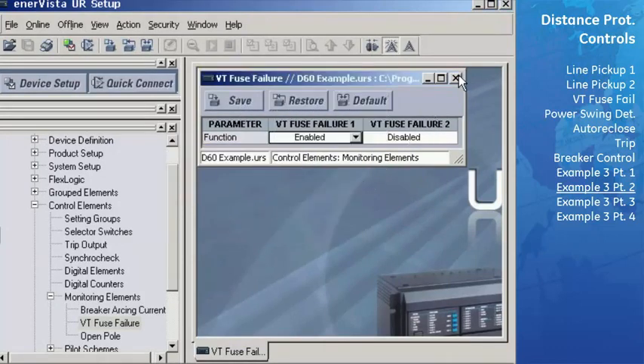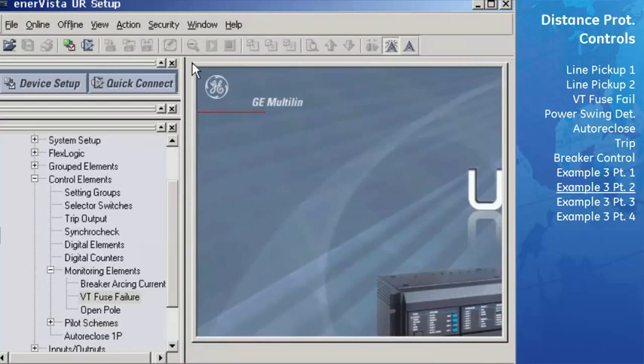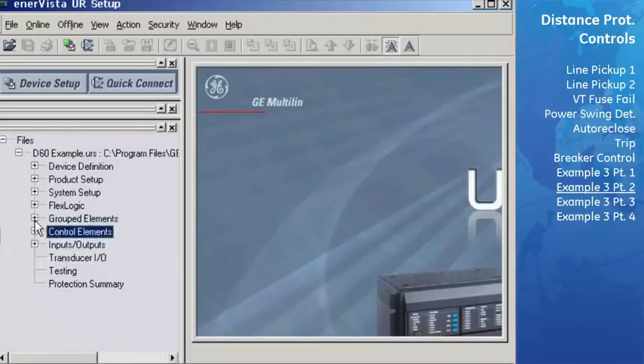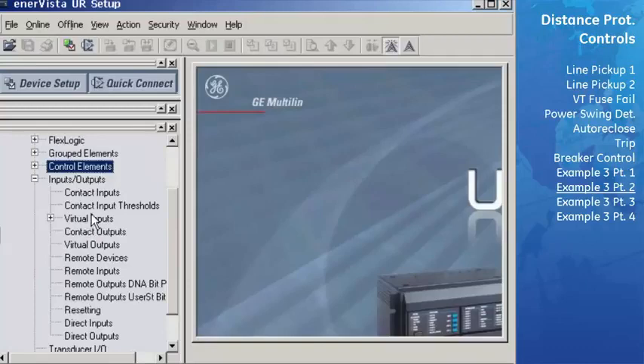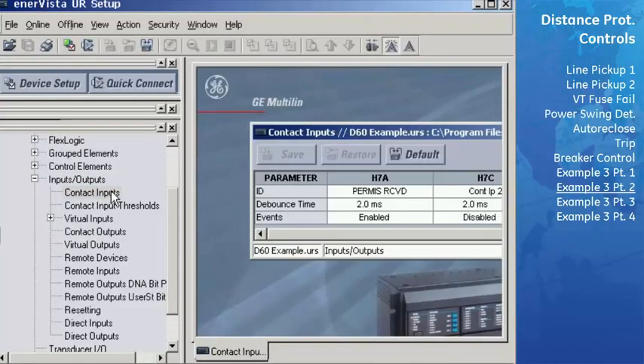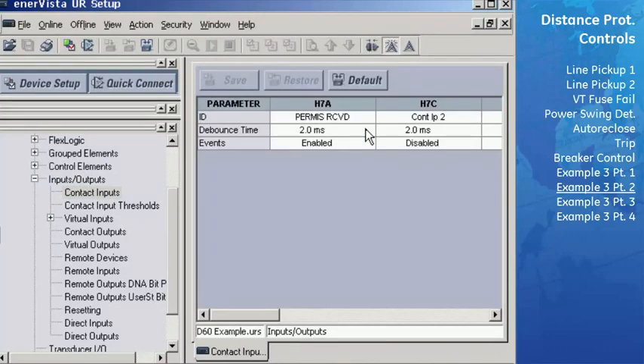The next function we will set up is the breaker control element. However, this element uses many contact inputs to validate the status of the breaker. Therefore, before creating the remainder of the settings, let's label the contact inputs and outputs that will be used. Go to Inputs Outputs, Contact Inputs. Change the name of contact H7C to Circuit Breaker 52A, which is our breaker status.